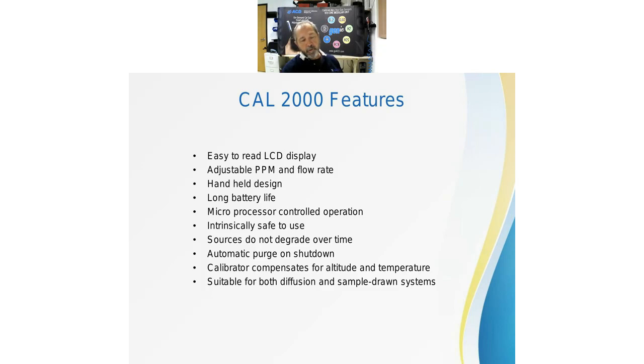These units can be used with sensors that are diffusion based, or sensors that have internal pumps that draw through them. You can shut off the pump on the Cal 2000 and allow the sample drawing pump to pull the sample in, or you can set the flow rate that you want if it's a diffusion based unit and calibrate it that way, like a cylinder would.